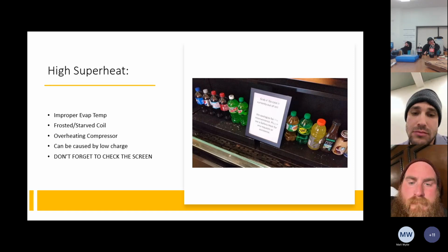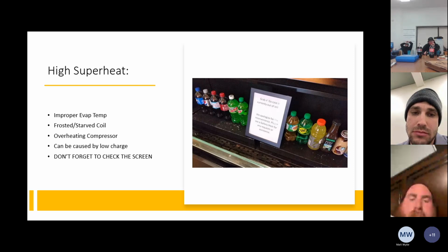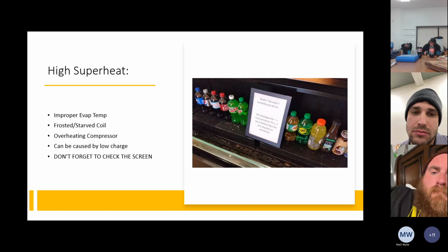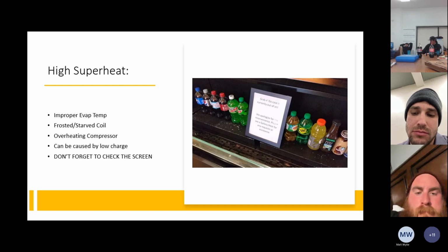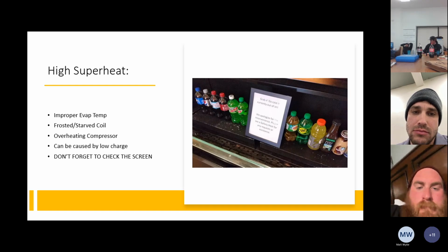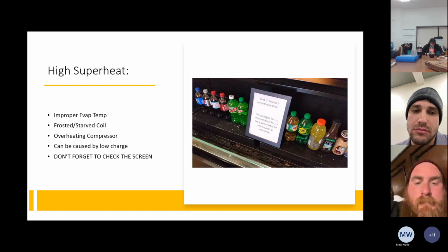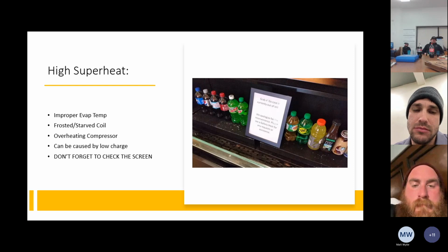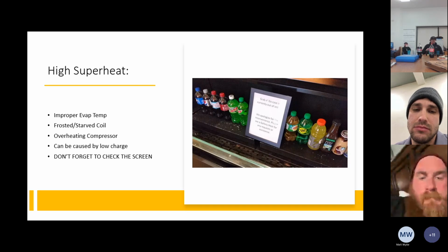Low temp or medium temp? Is it 10? Is it 10 for the superheat? Higher. 12? 20. Oh, 20. Wow. That's just to protect the compressor essentially. 20 degrees of superheat is what most compressor manufacturers say for minimum superheat, low or medium temp.